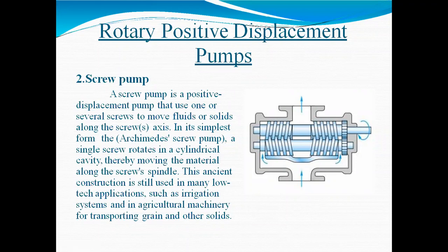Okay. Then it will forcefully throw this oil from the discharge port towards the application. Again, if you want to change the flow rate of this screw pump, we can change the speed of the motor. So once the speed changes, your flow rate can vary. Okay. So the working pressure of this type of pump is about 250 to 400 bar.